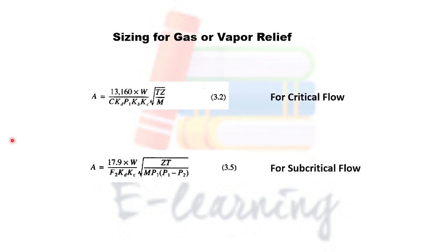If the incoming or relieving fluid is gas, we would use two equations. For critical flow, equation 3.2 of API 520 Part 1 would be used. For sub-critical flow, equation 3.5 of API 520 would be used.